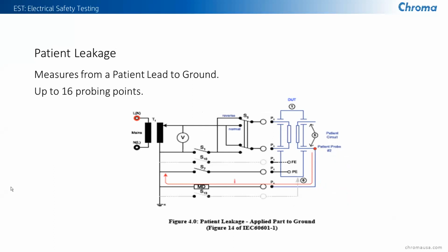Patient leakage follows the same principle, but there is more extensive testing. There are various tests to confirm that when the patient touches a device, they don't have access to leakage current that would cause a shock hazard. With this one, there are what they refer to as human impedance networks, and we'll go into that in more detail, including the variations for the different standards.